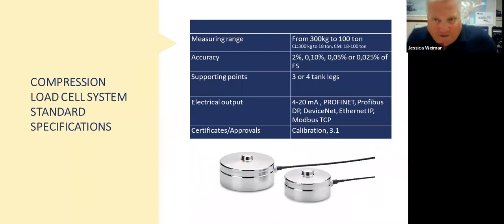So again, if you look here, we can talk through how you get to selection. Why does somebody use a beam cell versus a compression cell? A lot has to do with the actual measuring range, okay? A beam cell can be limited because of the physical construction of it. It can't handle extremely high loads. Our standard hygienic beam cells stop at 1,000 kilograms per cell. So with a 4-cell system, you could have 4,000 kilograms. The compression cell, because the load is sitting right down on the top of the cell, we build them up to 100 tons in the sanitary.